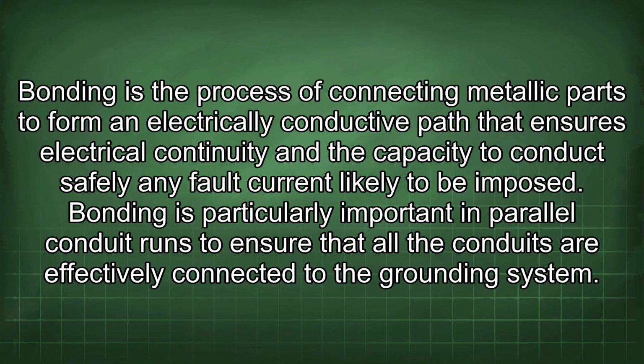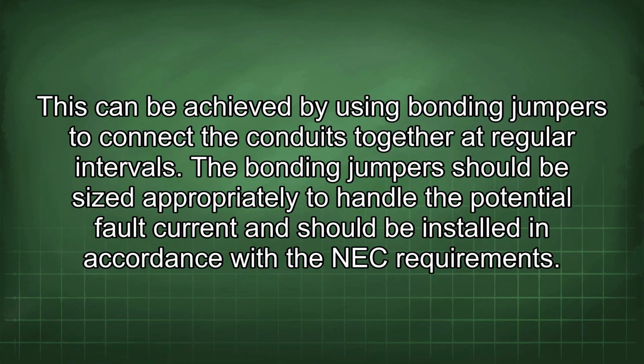Bonding is the process of connecting metallic parts to form an electrically conductive path that ensures electrical continuity and the capacity to conduct safely any fault current likely to be imposed. Bonding is particularly important in parallel conduit runs to ensure that all the conduits are effectively connected to the grounding system. This can be achieved by using bonding jumpers to connect the conduits together at regular intervals.